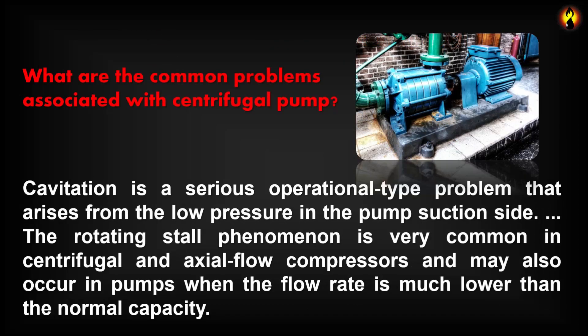What are the common problems associated with centrifugal pumps? Cavitation is a serious operational problem that arises from low pressure on the pump's suction side. The rotating stall phenomenon is very common in centrifugal and axial flow compressors, and may also occur in pumps when the flow rate is much lower than the normal capacity.